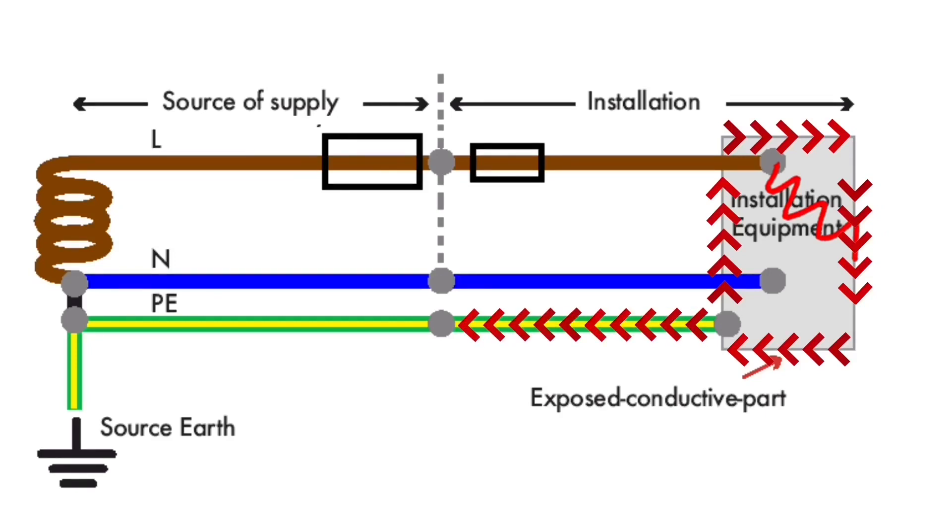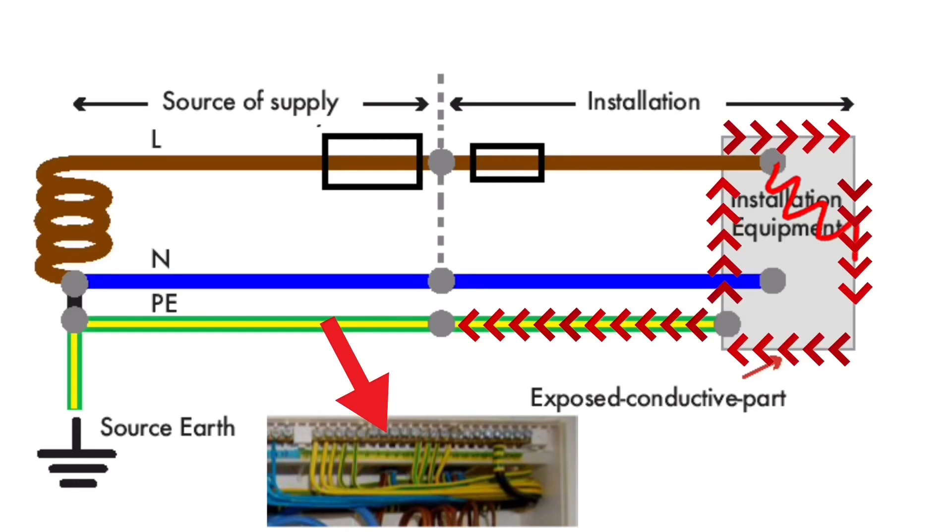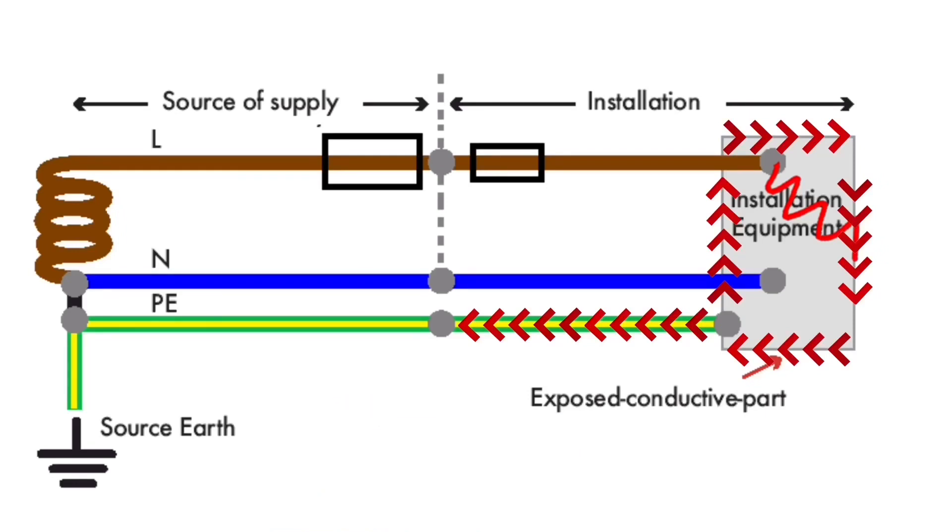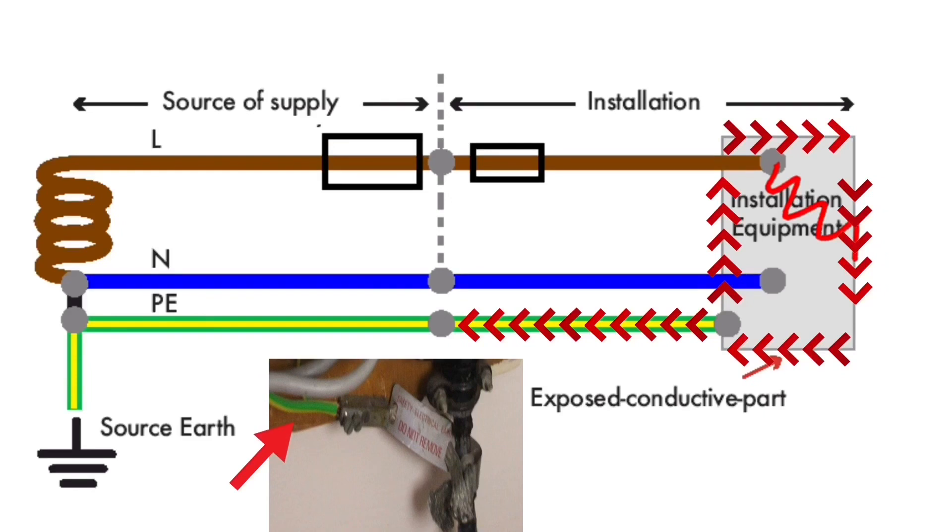This goes back to the earth terminal situated within the consumer unit which would become live. This is connected to the incoming earthing conductor which comes in with the meter tails. This earthing conductor becomes live.